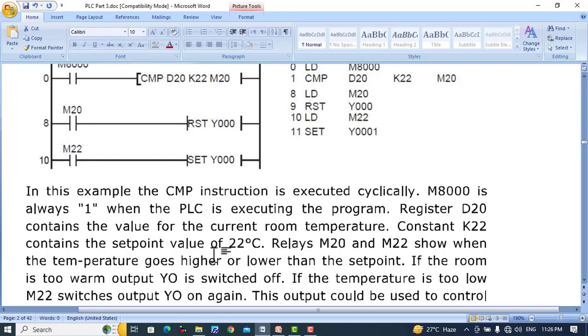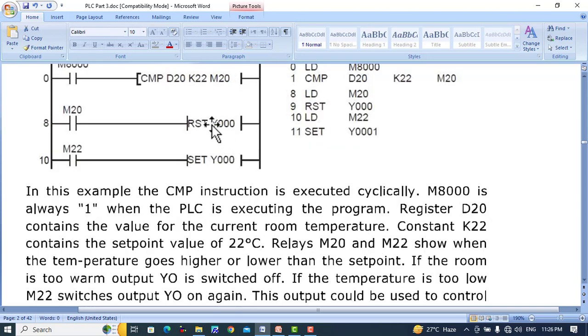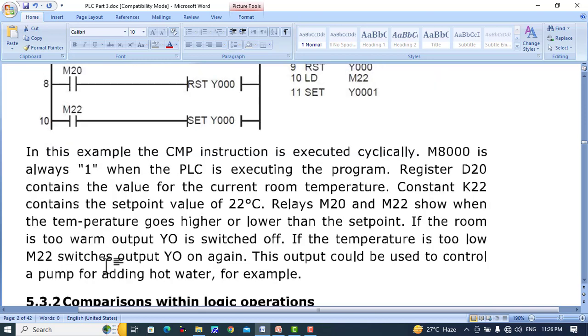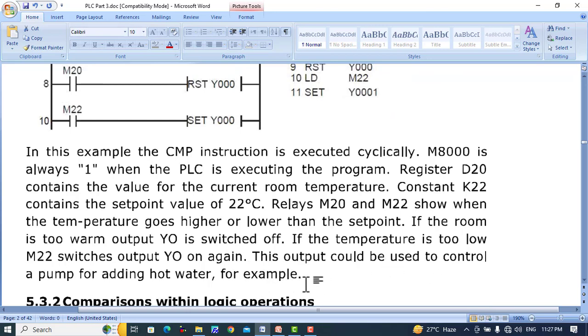Register D20 contains the value for the current room temperature. The constant K22 is used for the set point value. Relays M20 and M22 show when the temperature goes higher or lower than the set point. If the room is too warm, output Y0 is switched off via M20. If the temperature is too low, M22 switches output Y0 on again. This output could be used to control a pump for adding hot water when the temperature falls below K22.